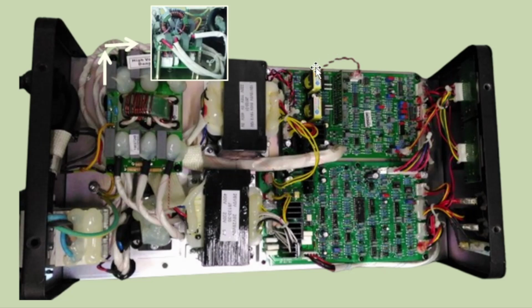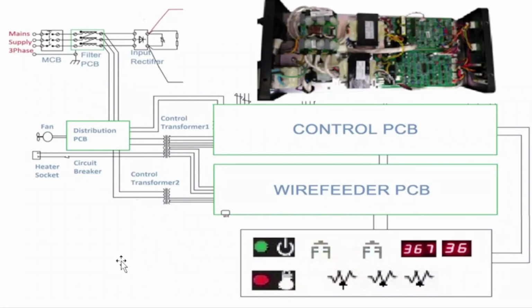Another 3-phase outputs from filter PCB are going to input rectifier. Outputs of the rectifier are positive and negative DC bus voltage, going to IGBT bridge. Here is the circuit diagram of the components that we have described. Input power, MCB, filter PCB, distribution PCB, rectifier block, control transformers 2 number, fan, heater socket and circuit breaker, control PCB, wire feeder PCB, front components.